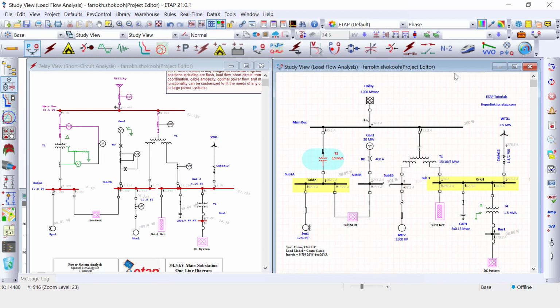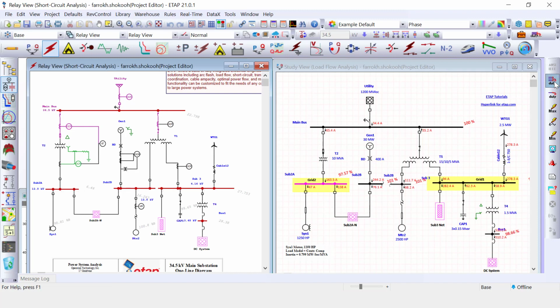I'm going to have a hard time finding a transformer with that high impedance, but I'll do it just to make a point. I can run load flow again, and I can see this bus went below 97-98%, so it's showing a warning. But if I run short circuit, I can see this particular fuse has a warning flag. So load flow wants to keep impedances at minimum so voltage drops are minimized, while short circuit wants impedances at maximum because it limits short circuit values. These are pulling the system in different directions.